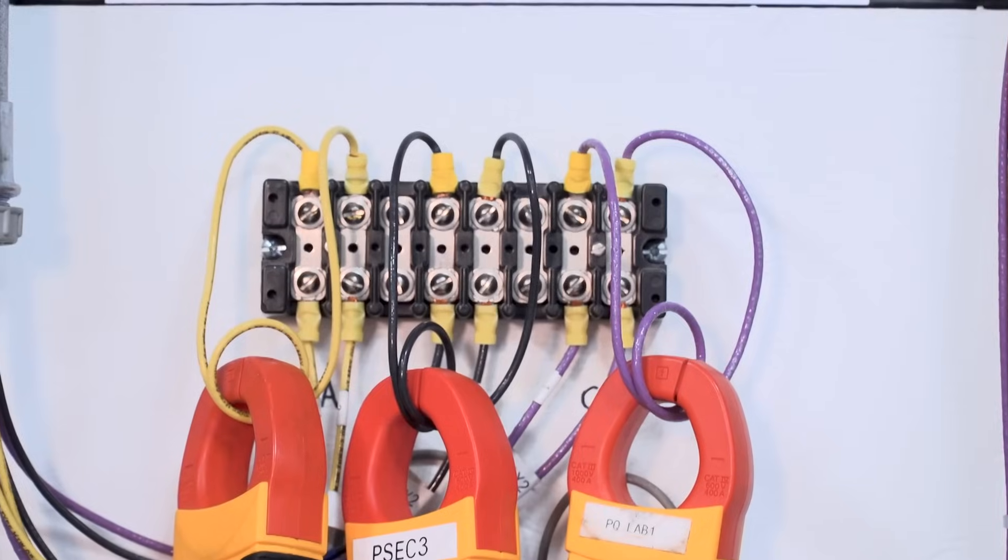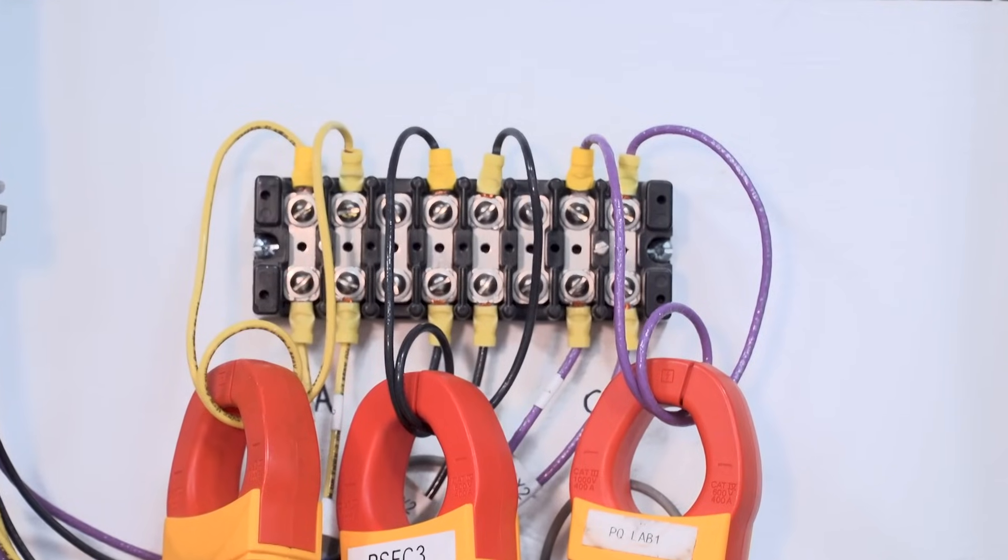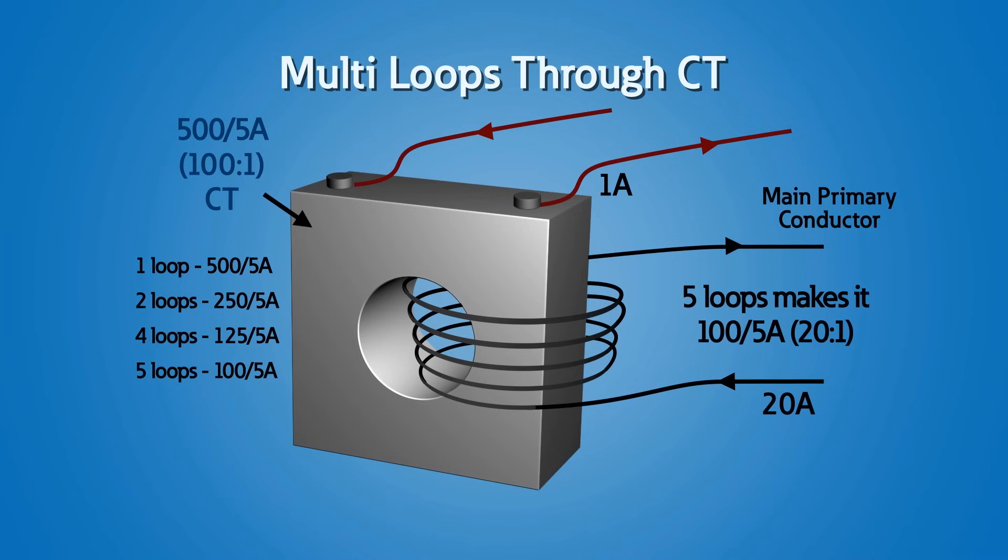Sometimes the current value is too small. A CT may not be accurate at less than 10% of its full load rating, so one way to increase the amount of current flowing through the core, especially for temporary metering, is to loop the primary wire several times through the core. For example, for a 500 to 5 amp CT or 100 to 1 ratio, looping the wire five times through the core will make the CT ratio 100 to 5 amps. So if 20 amps of current is flowing on the primary circuit instead of 0.2 amps, 1 amp of current will flow on the secondary, making the measurement more accurate.